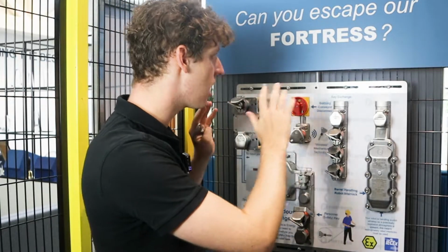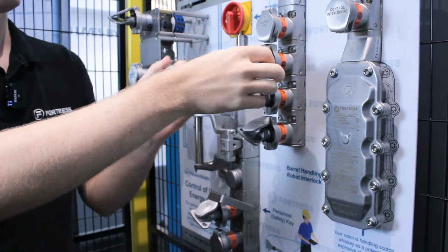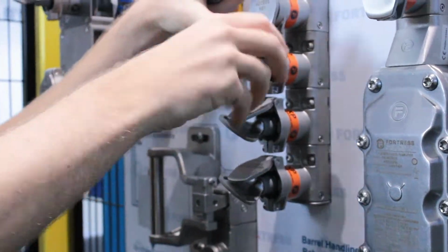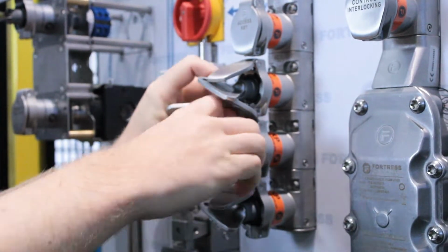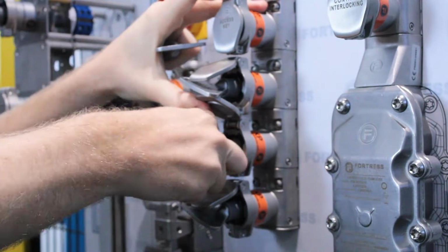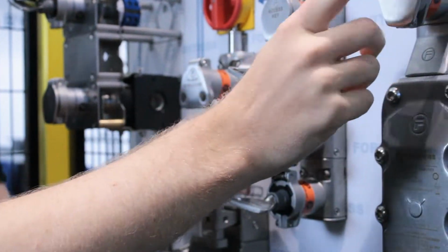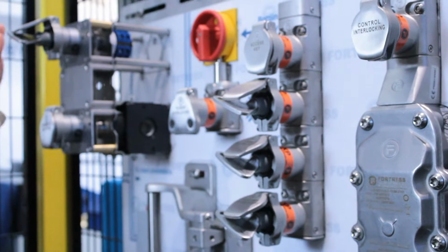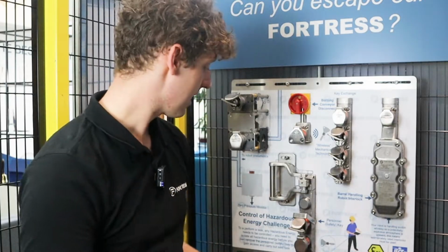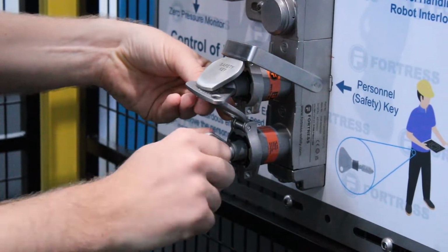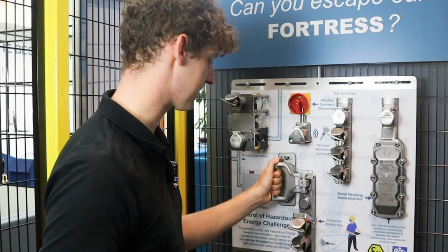Now, what prevents me from turning these three things back on again is that these keys are now trapped in place. Without the access key in this key exchange box, I cannot remove these keys and I cannot turn them, meaning that it's impossible for me to re-engage the isolator for the bottling conveyor, turn the machine on through this switch here, or uncontrol the pneumatics. So now I can take this access key and put it into our door module. Now this doesn't quite open the door for me yet. We've got one more trick up our sleeves.